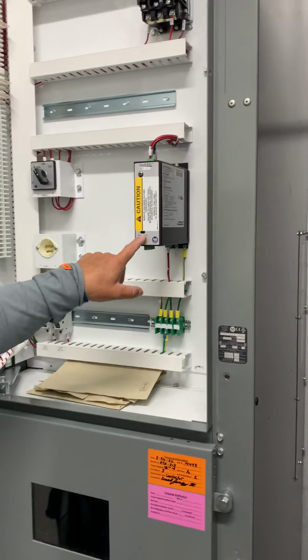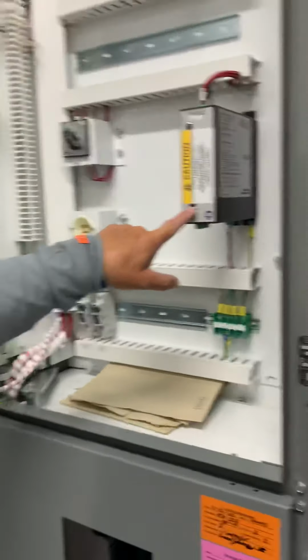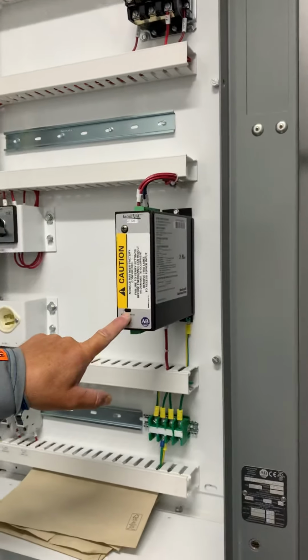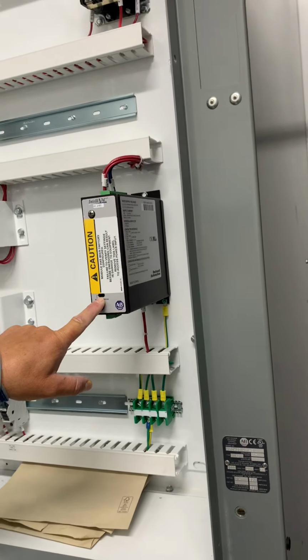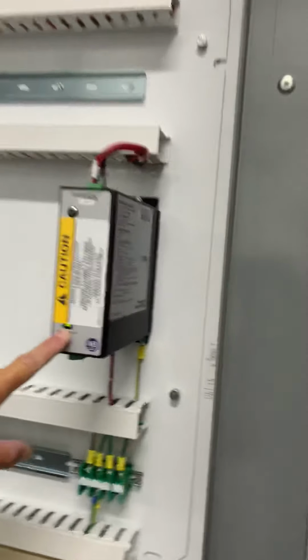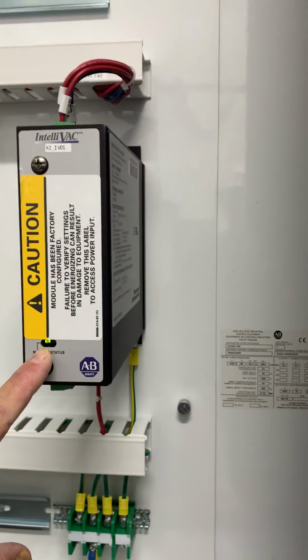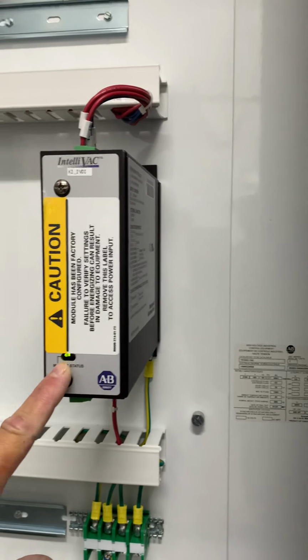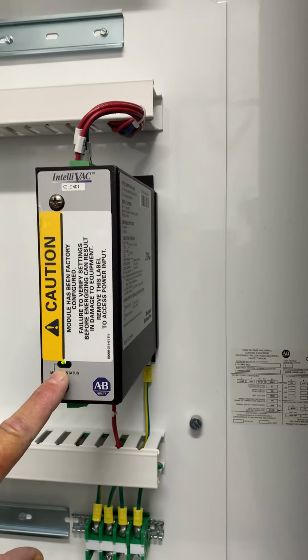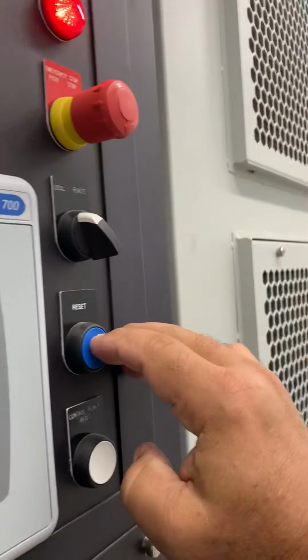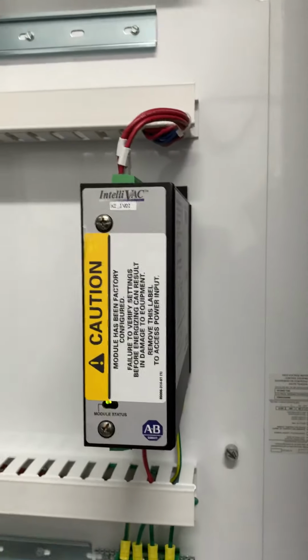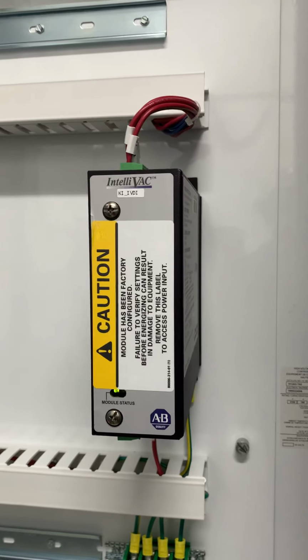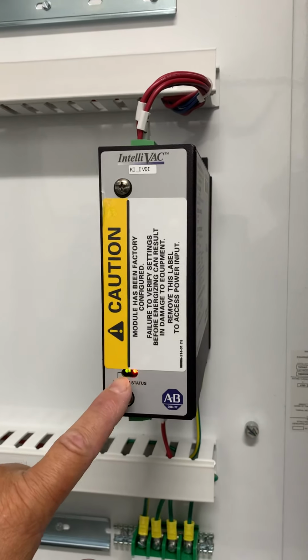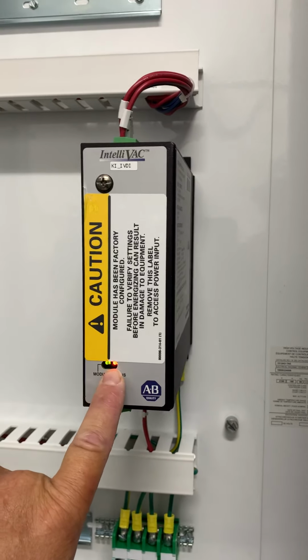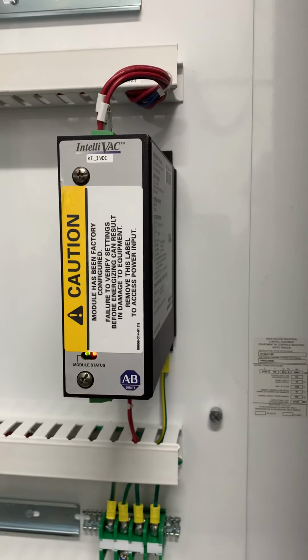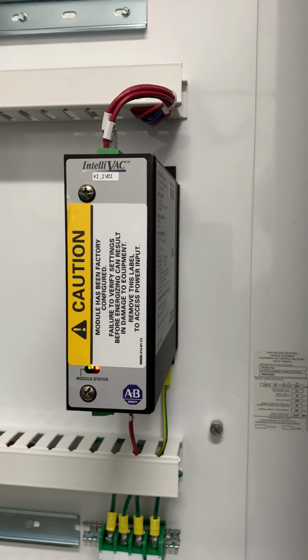What you'll notice is if you pull that E-stop and hit that reset, you pull the E-stop first, just twist and pull. So you notice how this lit up? It went to green. Okay, so it's ready. So we're good. If you hold down that reset and let it pull in the contactor, now you know that the module's good and the contactor's pulled in. Those are your indications on your tower light.